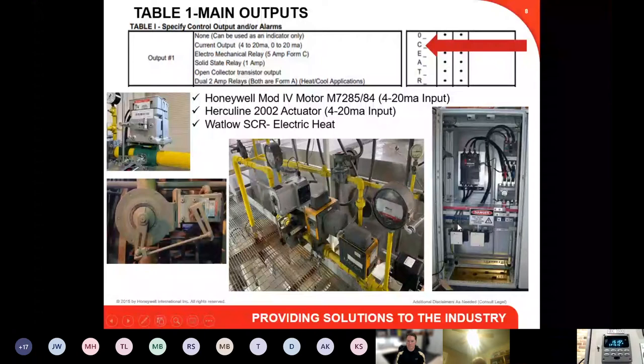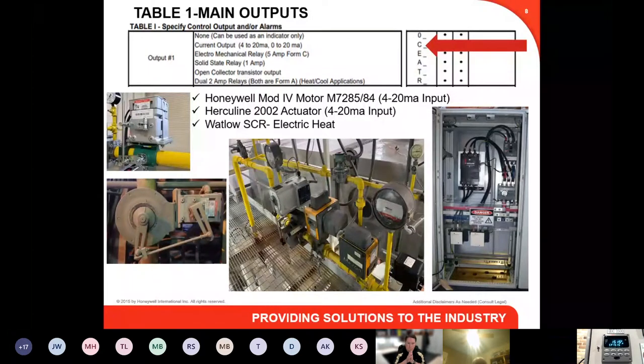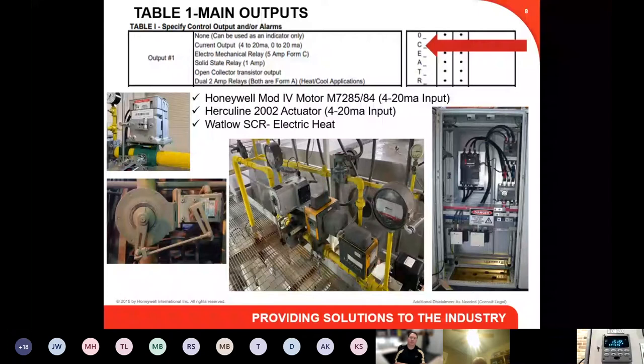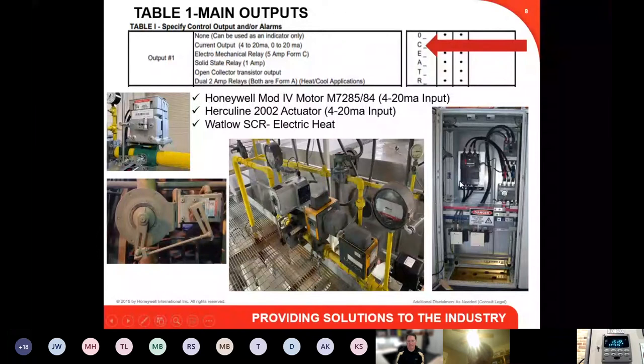When you get into PID loop control, a proportional current output signal is usually the best bet to achieve ideal control. The linear output gives a very accurate signal, is noise immune, can run for very long distances, and gives the process nice control — when tuned properly, it will line out at set point without fluctuations. Most times customers choose the C option when they have a motor or valve in the field that can accept a 4-20mA signal.